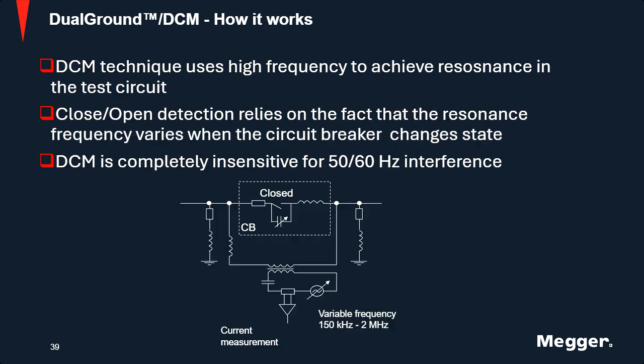So how does this work? This DCM is an attachment that can go with your circuit breaker analyzer test set. It uses a high frequency to achieve a resonance inside your breaker, either for closed or open detection. It relies on the fact that the resonance frequency varies when the circuit breaker changes state. DCM is completely insensitive to 50 and 60 hertz, so if you are testing in a live substation, that interference will not be a factor for the DCM. Another way to think about this is if your breaker is closing, you will have a very low current flow, whereas if it is open, you're going to have a lot of current flow when it comes to this variable frequency for dynamic capacitance testing.